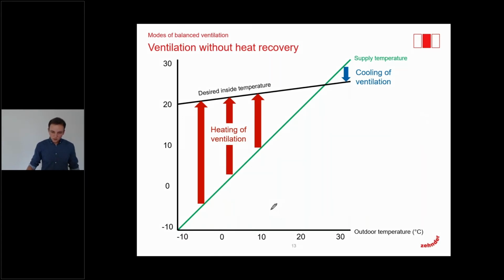So what you can see here, let me do a little example. If we have 0 degrees outside, we are here, and then we get in, the green line shows the supply air temperature. Of course, we get in supply air temperature at 0 degrees. And now we need to heat up the air to our desired level. So this amount of energy needs to be provided by the central heating system.